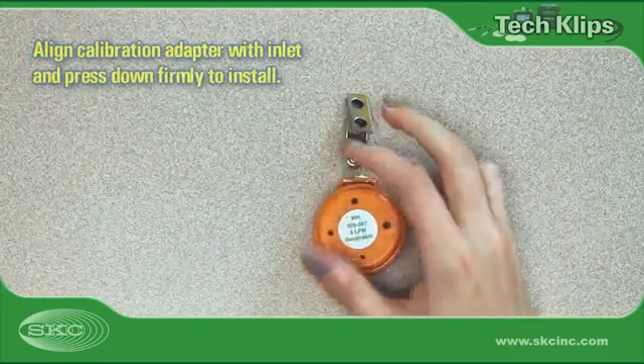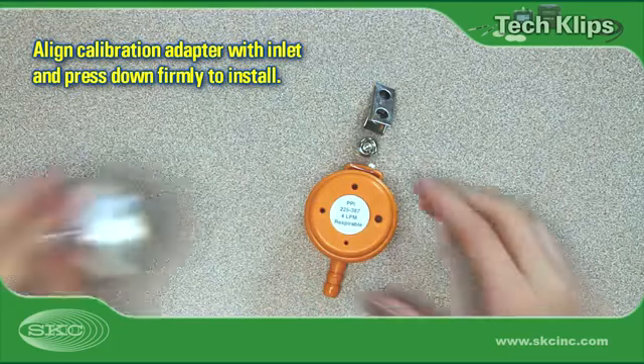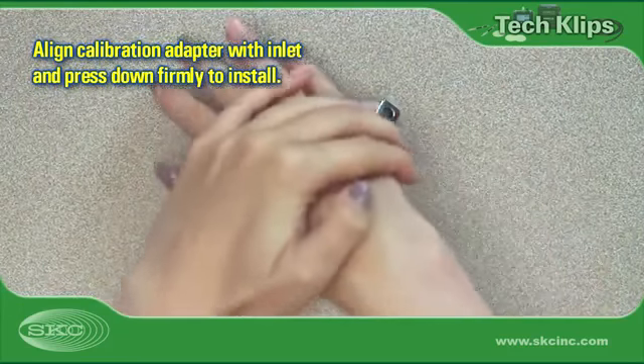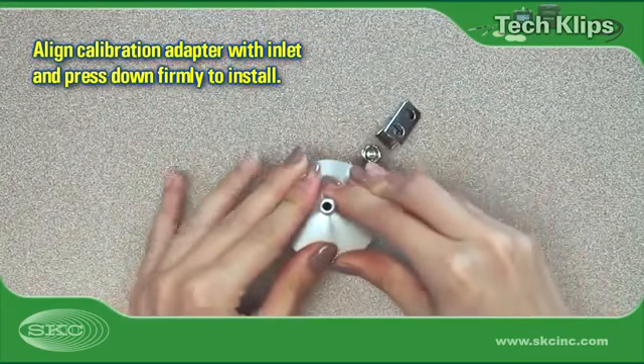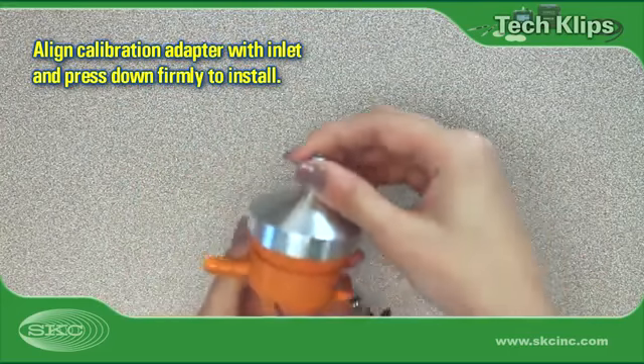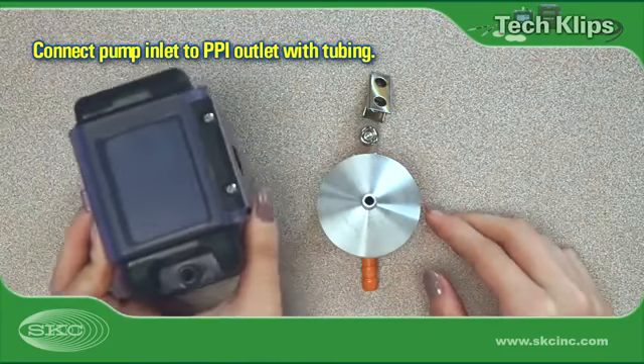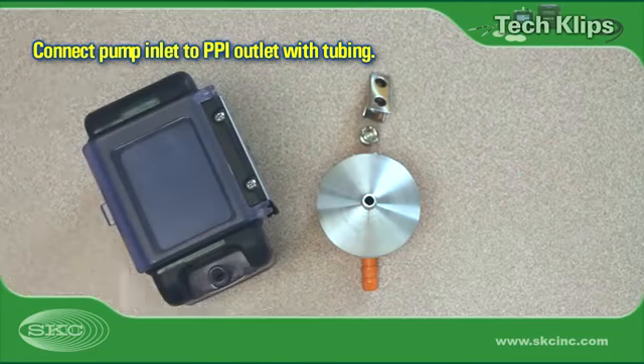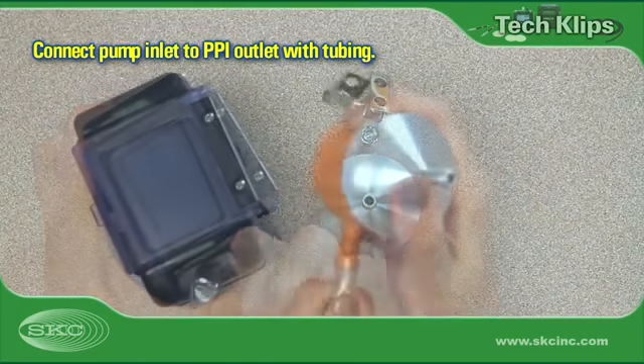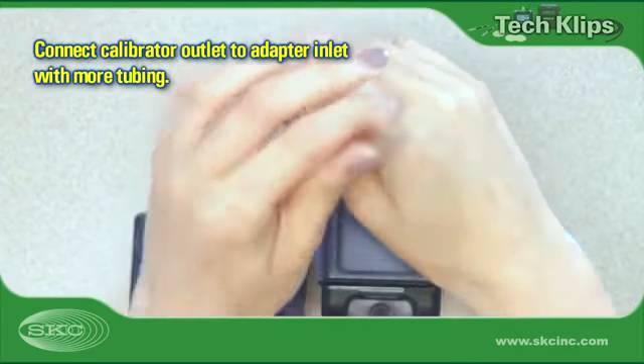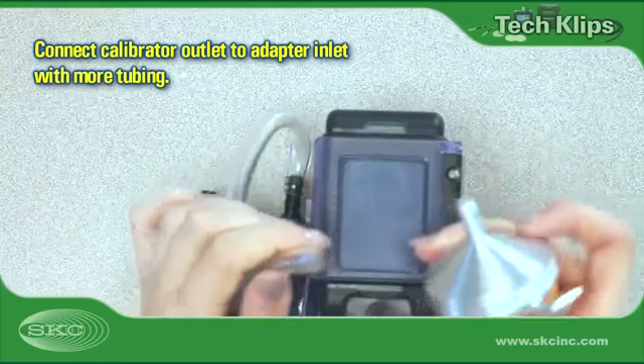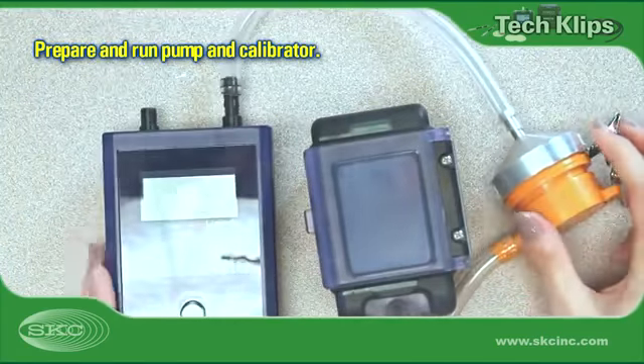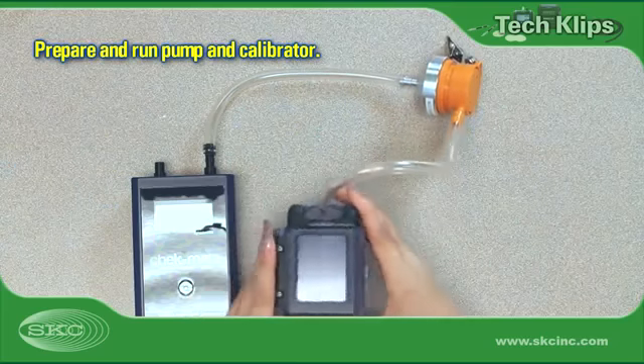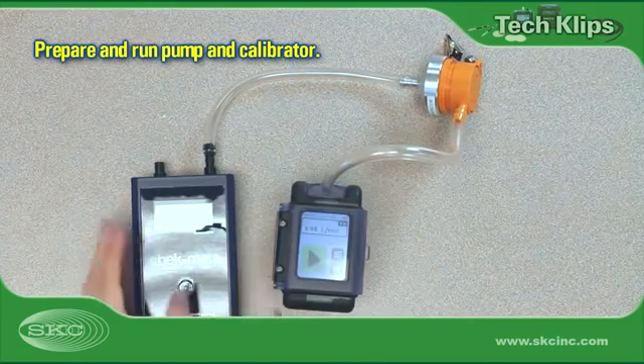Remove the protective cap from the sampler exhaust. Install the calibration adapter on the sampler inlet. Be sure to establish a good seal. Connect the pump inlet to the sampler exhaust with tubing. Use a second length of tubing to connect the calibrator to the calibration adapter. Run the pump for 5 minutes and prepare the calibrator according to manufacturer instructions.